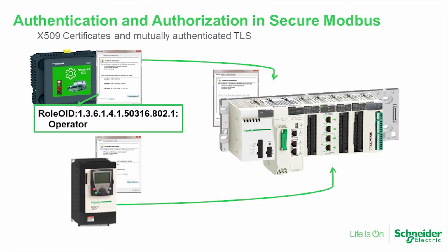A little bit about the authentication. We're using secure X509 certificates to prove identity. Signed by a certificate authority is the recommended way, but self-signed certificates could be used. We don't recommend that at all. Embedded in the certificate is an OID that we're calling a role. IEC 62351 has a similar mechanism, and we're kind of following along with that.